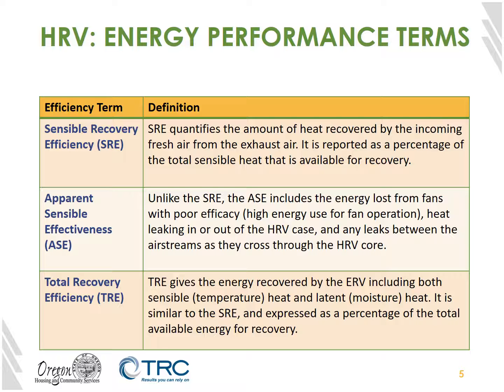ASE, or apparent sensible effectiveness, is calculated by including the heat transfer from the high energy using fans to the airflow, as well as any heat that leaks in or out of the HRV case, and any leaks that may happen between the air streams as they cross through the HRV core. It's also expressed as a percentage and is equal to the temperature rise of the incoming air divided by the temperature difference between indoor and outdoor air.